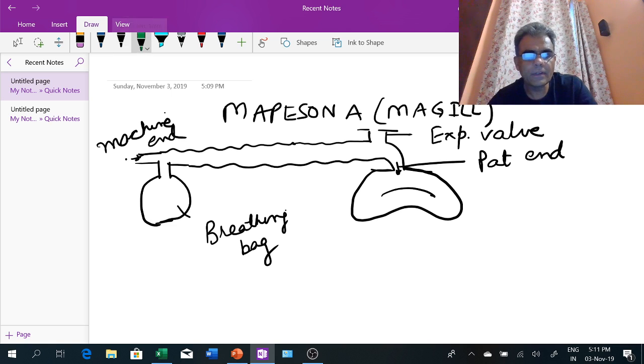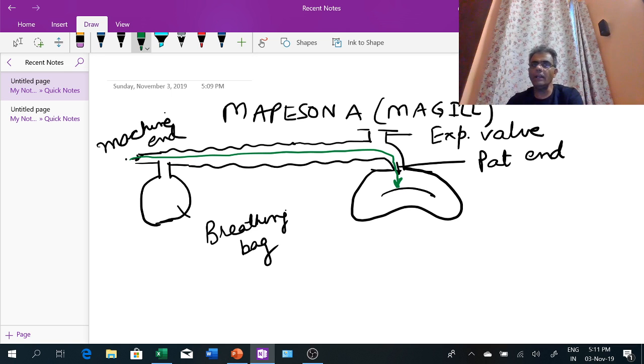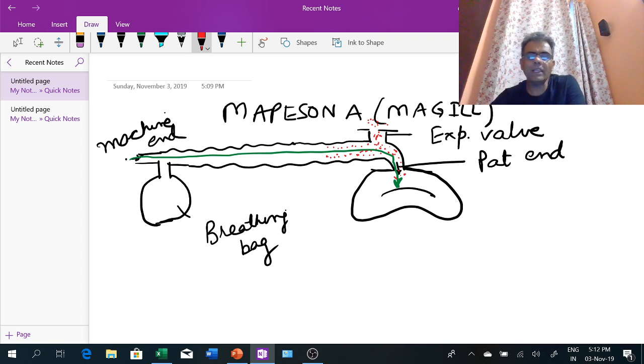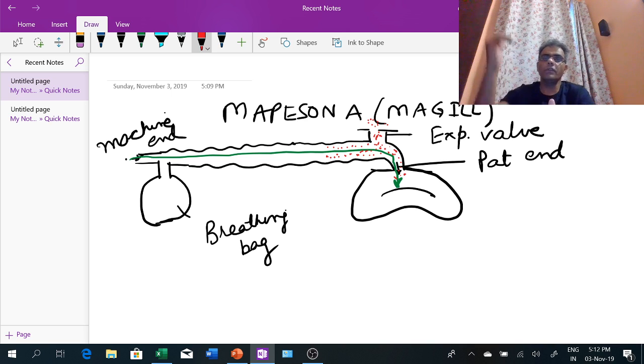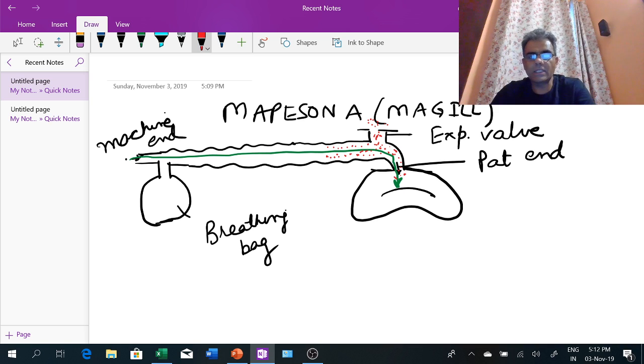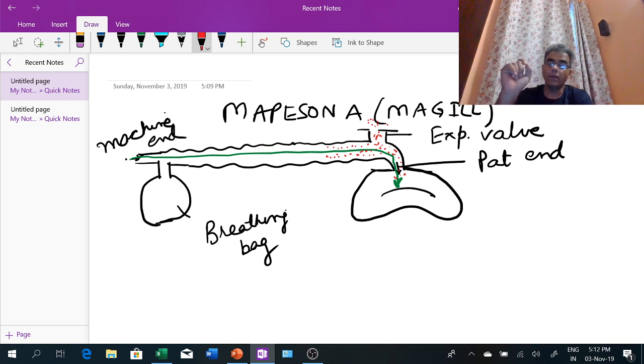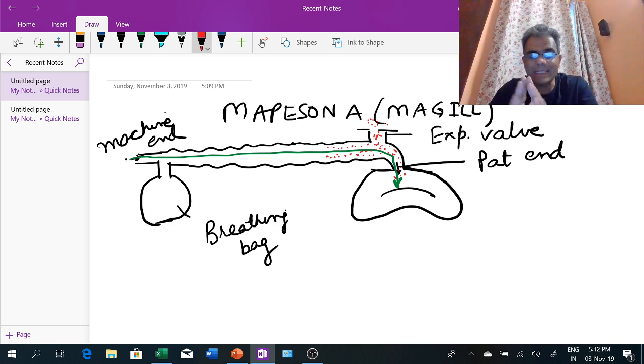Fresh gases coming from the machine, shown here as a green line, are directly delivered to the patient. The expired gases, shown as red dotted lines, mostly vent out into the atmosphere through the expiratory valve. However, some of these gases go back into the tubing and will be re-inhaled by the patient in the next breath — that is called re-breathing, which we never want.